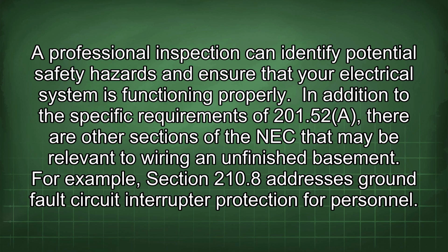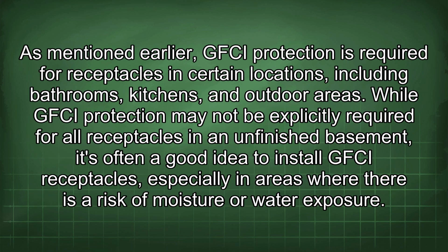In addition to the specific requirements of 201.52a, there are other sections of the NEC that may be relevant to wiring an unfinished basement. For example, Section 210.8 addresses ground fault circuit interrupter protection for personnel. As mentioned earlier, GFCI protection is required for receptacles in certain locations, including bathrooms, kitchens, and outdoor areas. While GFCI protection may not be explicitly required for all receptacles in an unfinished basement, it's often a good idea to install GFCI receptacles, especially in areas where there's a risk of moisture or water exposure.